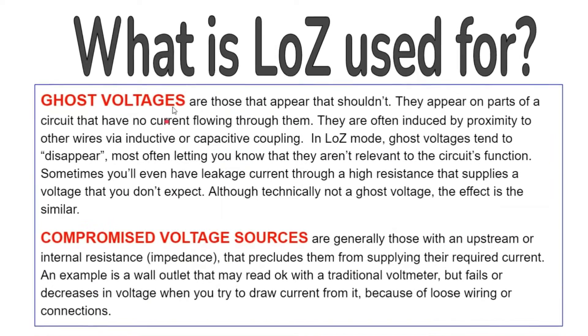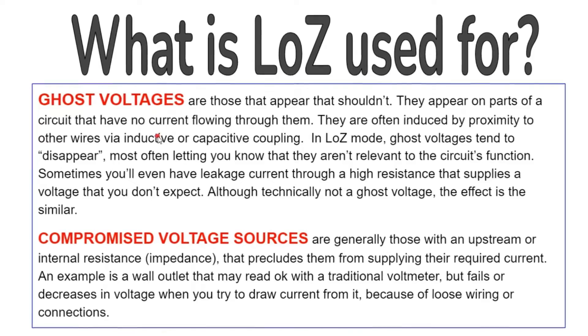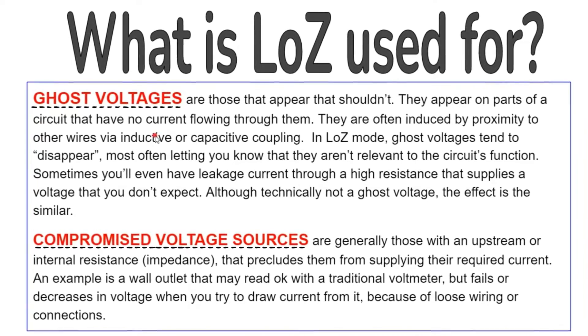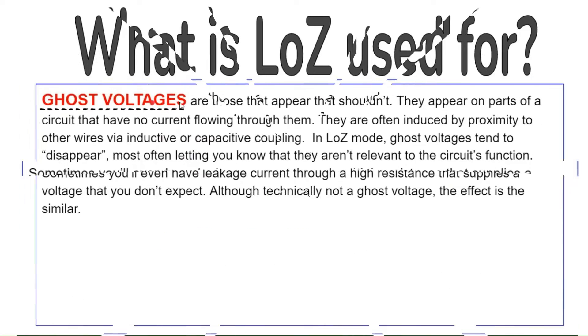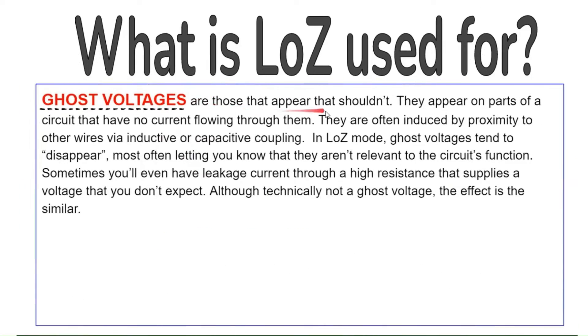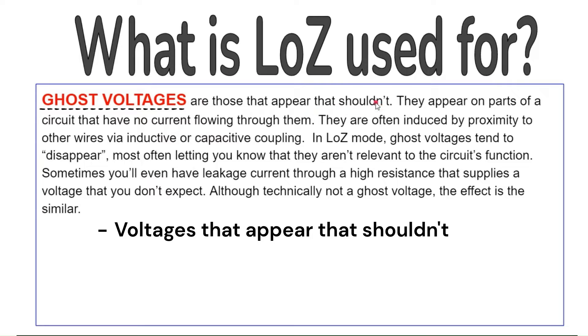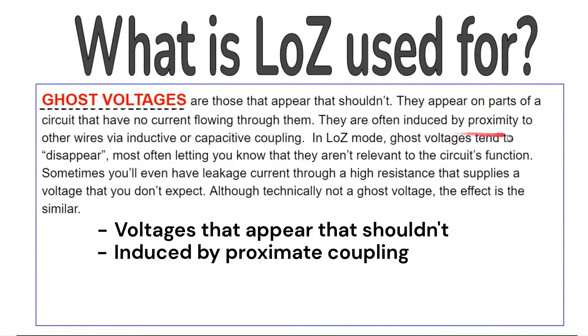Low Z can be used to detect ghost voltages and compromised voltage sources. Ghost voltages are those that appear that shouldn't. They appear on parts of a circuit that have no current flowing through them. They are often induced by proximity to other wires via inductive or capacitive coupling.